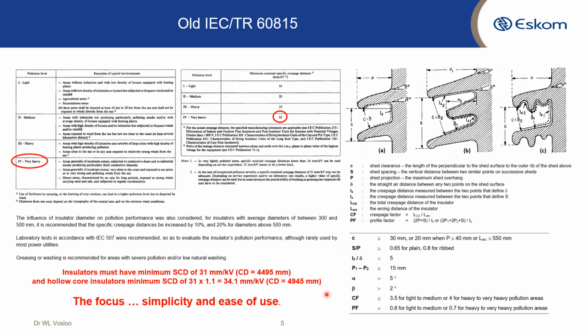And at the end of the day, the focus of the old 815 was simplicity and ease of use. For that same area, we would have said either greasing or washing, but we know that doesn't work from our practical experience. So we would specify a hydrophobicity transfer material.